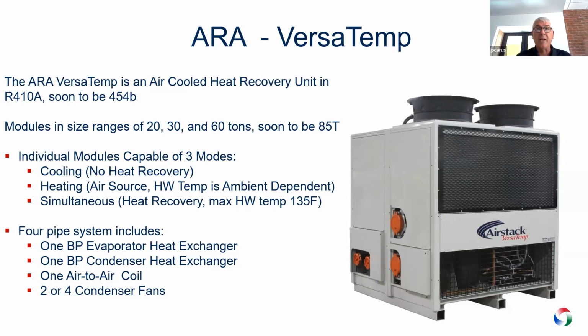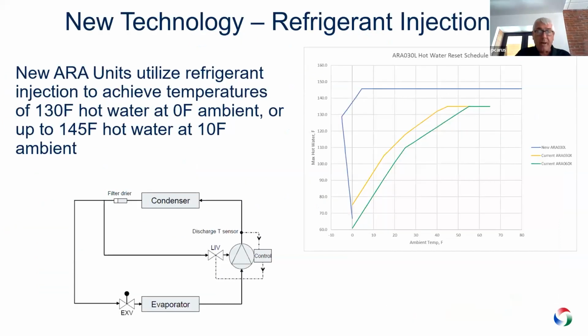If you happen to be in simultaneous mode, you're doing as much heat recovery as you can and then getting rid of whatever is not needed at that point. Talked about this technology a little bit, but just to give a better sense, this new ARA product line using refrigerant injection, effectively through a solenoid valve, throws some refrigerant into the top cap, expands the envelope, does, I call it enhanced motor cooling, and lets you expand the envelope all the way so that you can do -4 degrees and 130, 135.